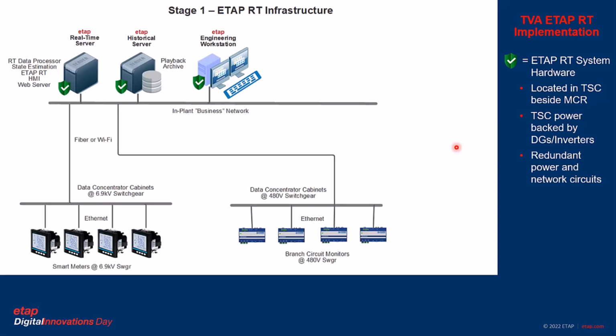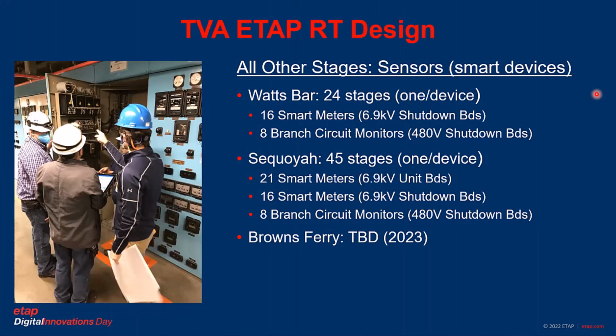And the idea there is it'll give the plant flexibility to install this without having to plan around operating plant equipment. Now let's talk about all the other stages, which are the sensors, actually connecting these sensors up to the plant equipment. At Watts Bar, we'll have 24 stages. There's one stage for each device, and that gives the plant the flexibility if they're going to be in any of these metering compartments, like on the 6.9 kV shutdown boards or the 480 volt shutdown boards, they can choose to install these devices. And as they install each device, the infrastructure is already there. So once it's installed, it'll start communicating back to the ETAP server.